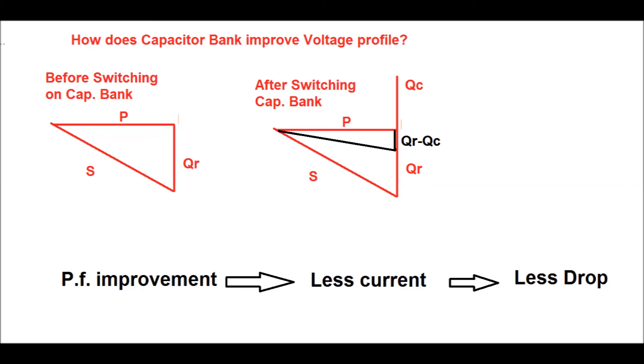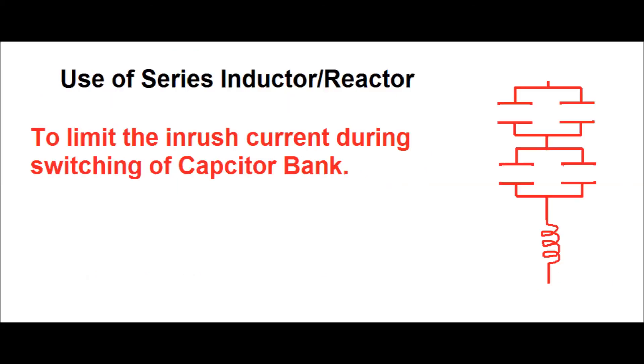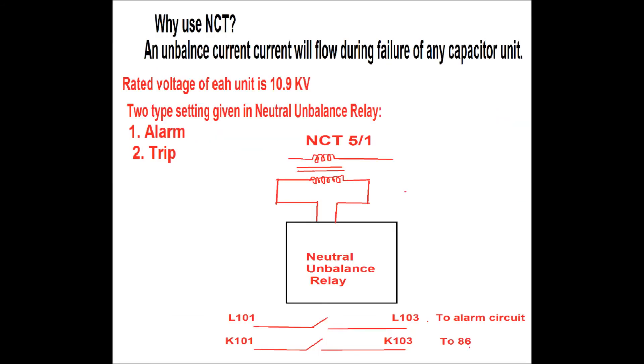What is the use of the series reactor in each capacitor bank? When we switch on the capacitor bank, the capacitor units act as a short circuit and will take a huge amount of inrush current. To limit this inrush current during switching on of the capacitor bank, series reactors are used.